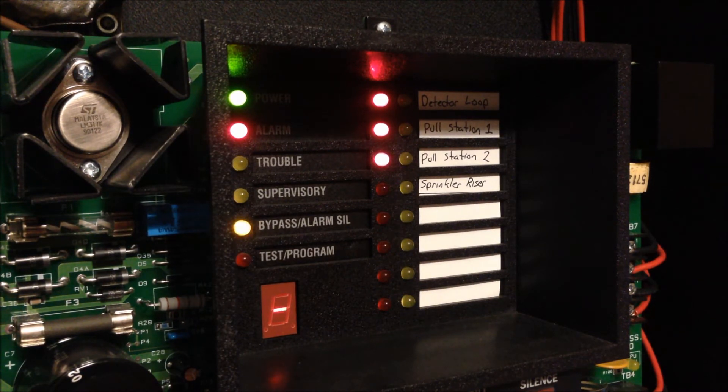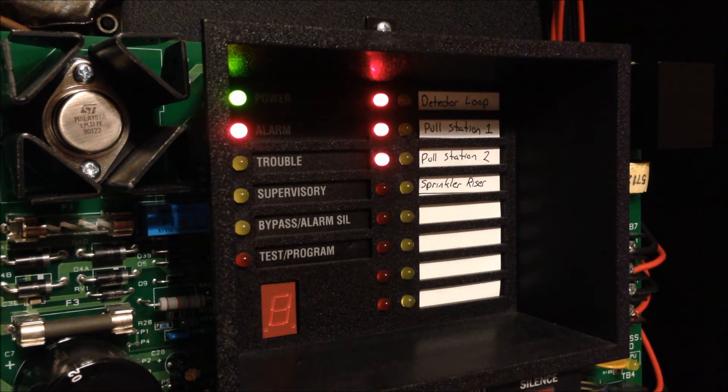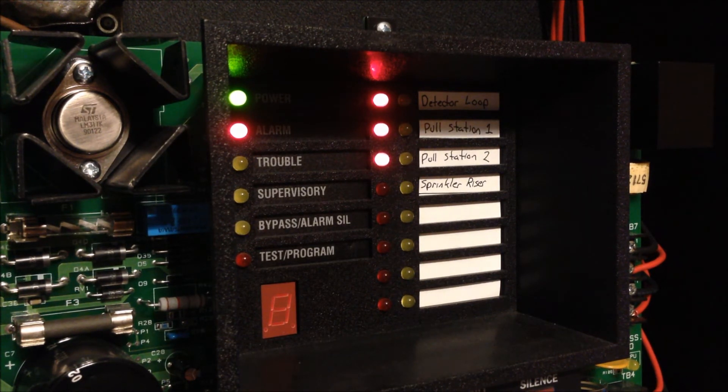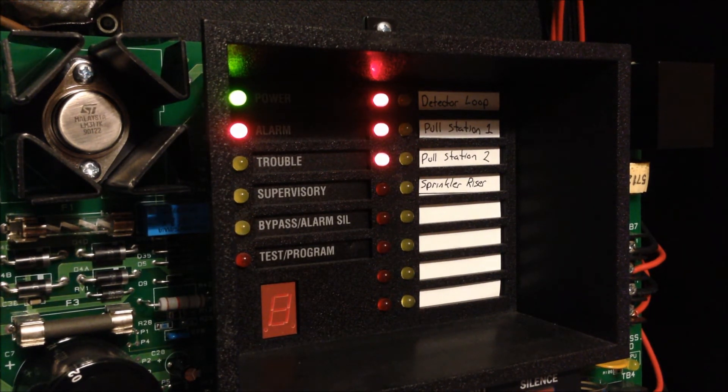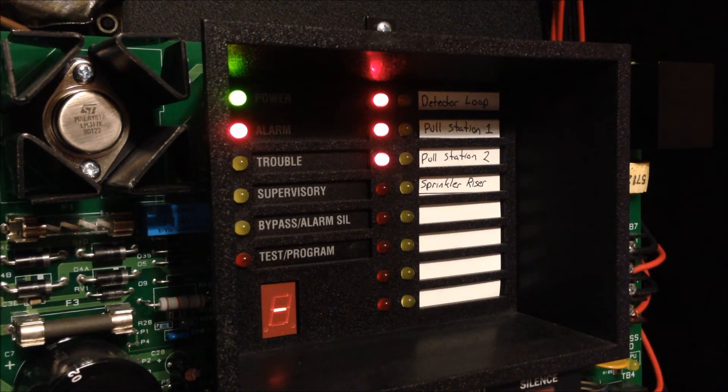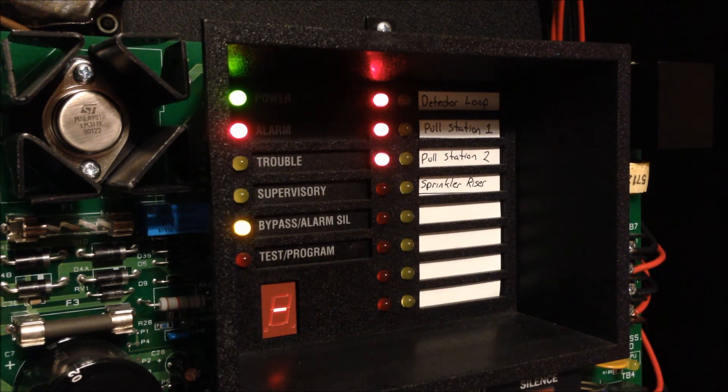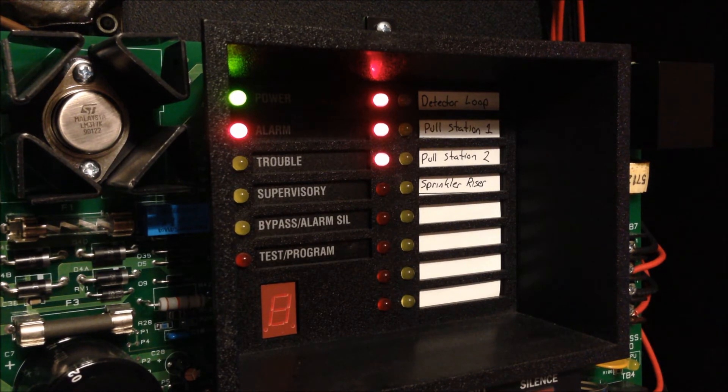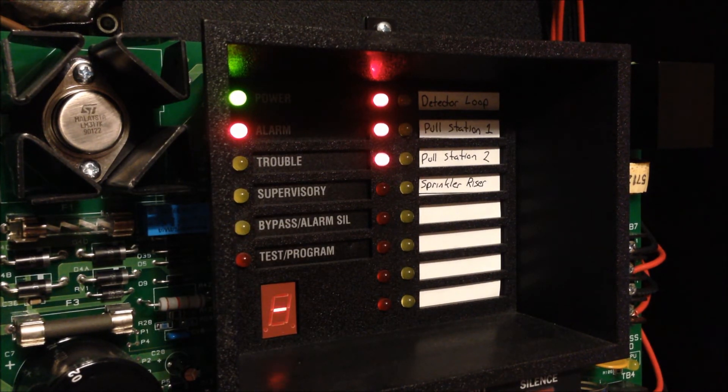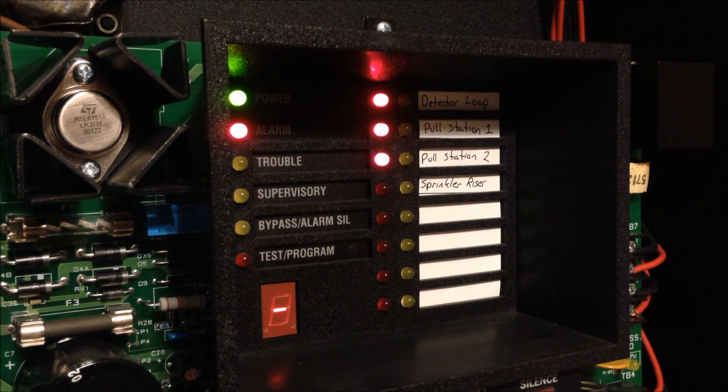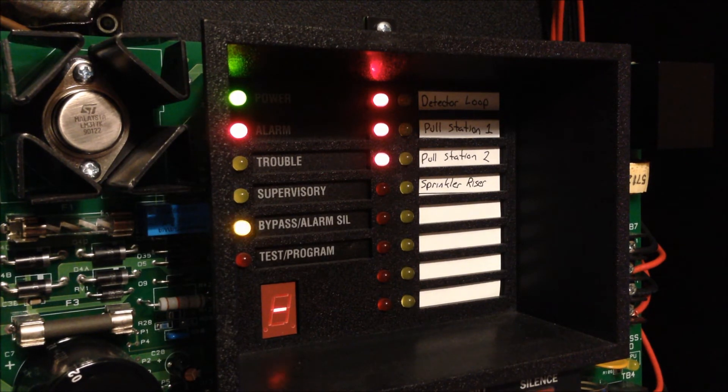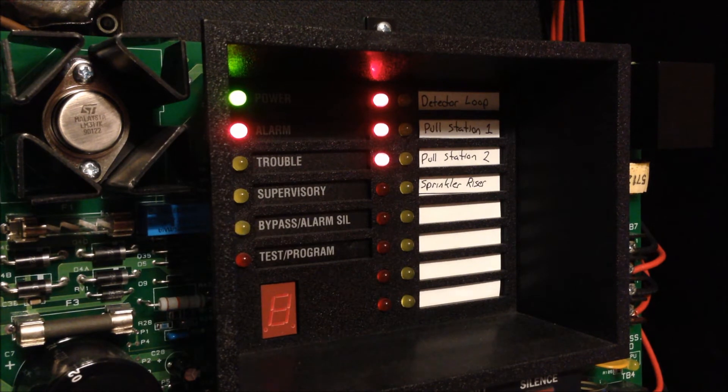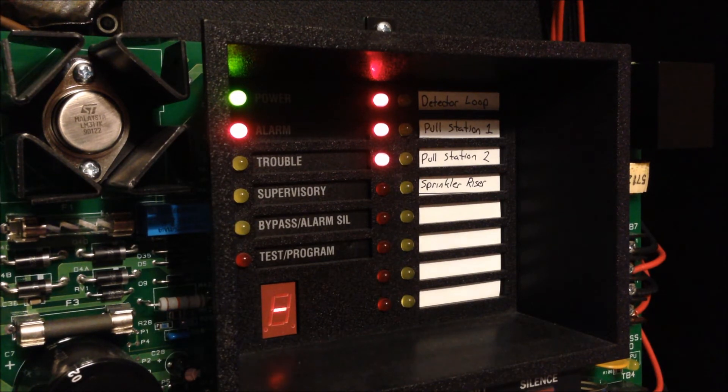So as you heard as the alarms were cycling around, for each zone that's in alarm it's obviously going to annunciate that through the pulses of the chime. But when it has multiple zones in alarm what it'll do is it'll sound 3 rounds of each zone that's in alarm before moving on to the next and it just does that sequentially down the board.